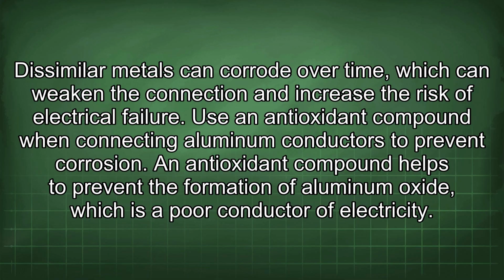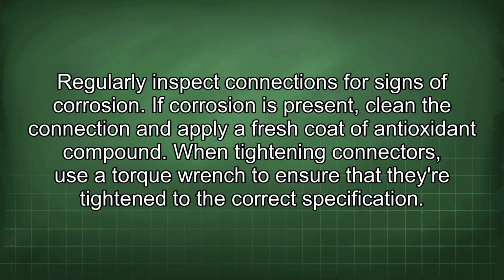An antioxidant compound helps to prevent the formation of aluminum oxide, which is a poor conductor of electricity. Regularly inspect connections for signs of corrosion. If corrosion is present, clean the connection and apply a fresh coat of antioxidant compound. When tightening connectors, use a torque wrench to ensure that they're tightened to the correct specification.